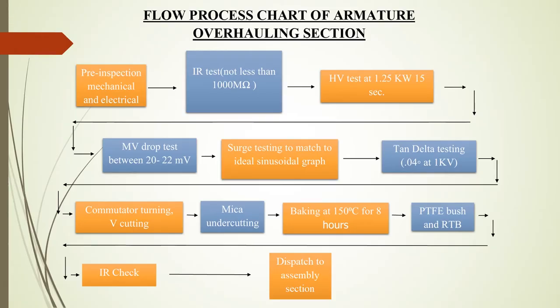In the armature overhauling section, armatures come in after fitting from the stripping section. Pre-inspection is carried out in the form of mechanical and electrical inspection. In mechanical inspection, the physical dimensions obtained are matched with standard values. After that, an IR test is carried out in which the value should be more than 1000 Mega Ohms. Then a high voltage test on power coils of the armature is done in which leakage current is measured — for good quality insulation, leakage current should be less than 25 milliamperes per kilovolt. A millivolt drop test is performed across each segment of the commutator with a 150 ampere DC supply to get a voltage drop between 20 to 22 millivolts. Surge testing is then done in which insulation of conductors is checked and compared with the standard sinusoidal graph. A tan delta test is done to check the quality of insulation.